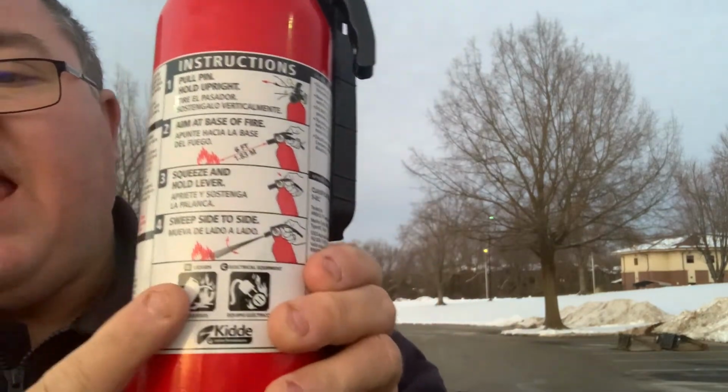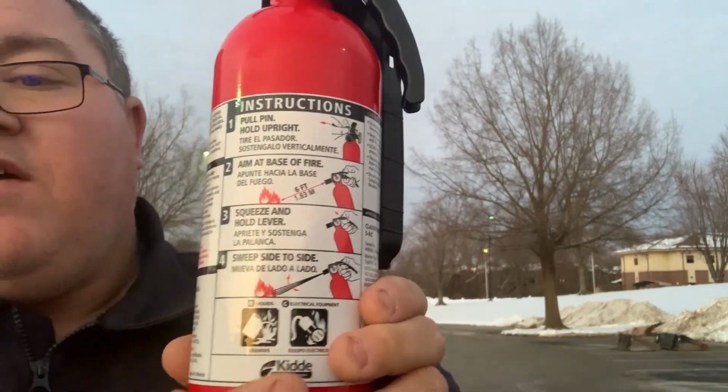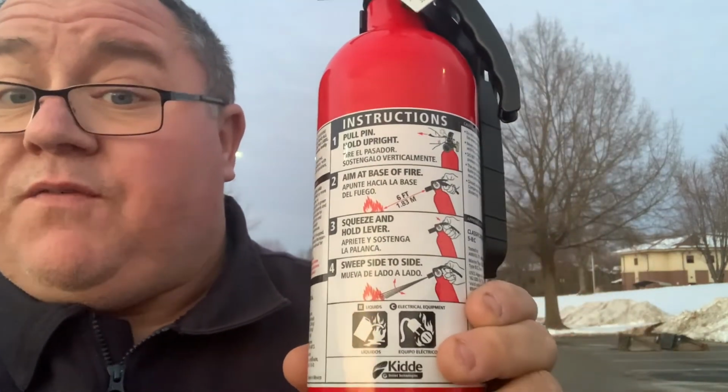Now this one is only a B and C, for flammable liquids or energized equipment. If you can get an ABC, it's better. But this is a good kitchen extinguisher. For your shop or for your barn, I would get an ABC that was bigger than this. Get a 10-pound, that's what that other one was. A 10-pounder, and it's got a hose on it, where this one you have to point the nozzle. The other one has a hose that you can sweep side to side. So even if you can just carry it to the fire and set it down, you still have the ability to use it.